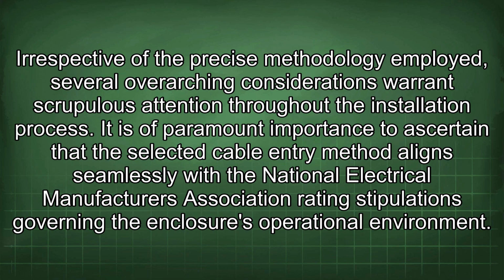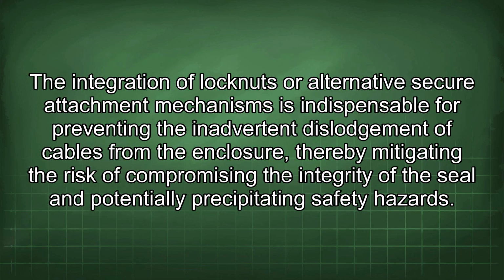It is of paramount importance to ascertain that the selected cable entry method aligns seamlessly with the National Electrical Manufacturers Association rating stipulations governing the enclosure's operational environment. The integration of lock nuts or alternative secure attachment mechanisms is indispensable for preventing the inadvertent dislodgement of cables from the enclosure, thereby mitigating the risk of compromising the integrity of the seal and potentially precipitating safety hazards.